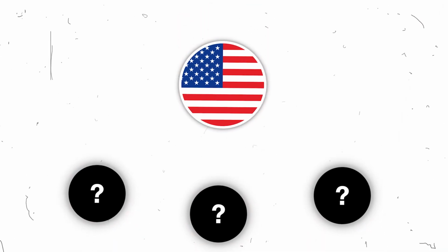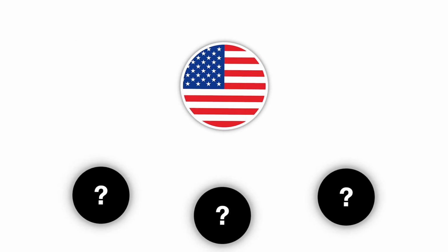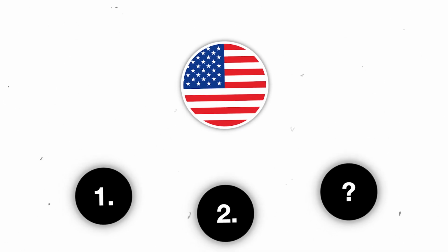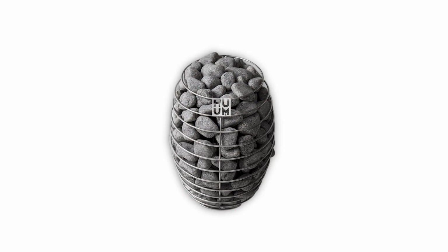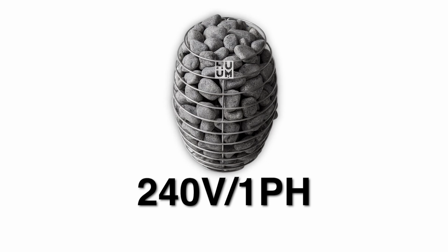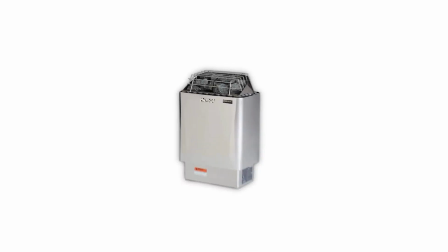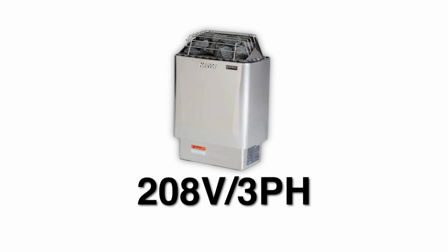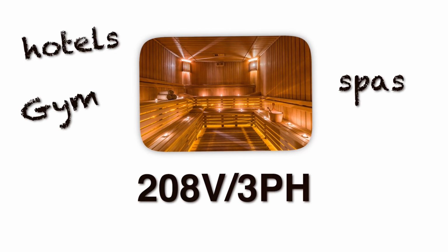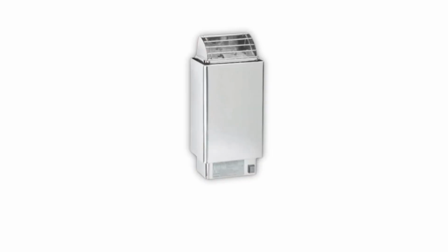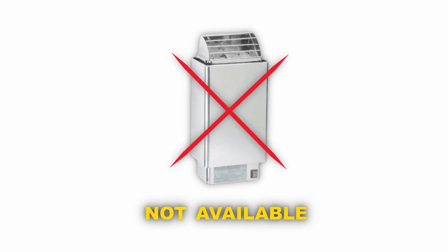In the US, we typically have three different types of voltage and phase combinations, out of which two are really available. The most common combination that almost all electric sauna heaters require is 240 volt one phase. Some sauna heaters with commercial configurations are offered at 208 volt three phase power to fit the electrical infrastructure that commercial buildings utilize. There have been some 120 volt one phase sauna heaters in the past, but these are basically not available or produced anymore.